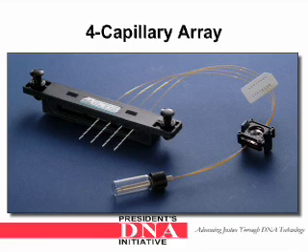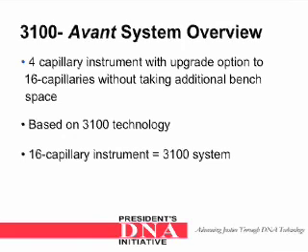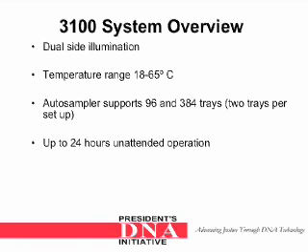This is an example of what a 4-capillary array looks like. The 3100 Avant system is a 4-capillary instrument with an upgrade option to 16 capillaries without taking additional bench space. The Avant system is based on 3100 technology. The original 3100 system was for a 16-capillary instrument. The 3100 has dual side illumination, a temperature range from 18 to 65 degrees Celsius, and the auto-sampler supports 96 and 384 trays, two trays per setup. It can be left to run up to 24 hours with unattended operation.